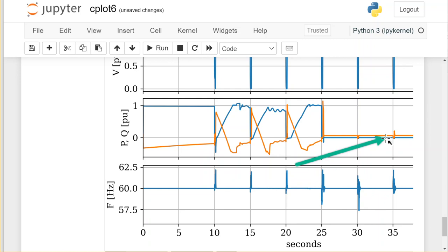So this is an informational test. It was stable down to a pretty low short circuit ratio. So in fact, right in this range here, the short circuit ratio was 3. And when it went down to 2.5, the plant did not come back. So this is a more severe scenario where we're having these faults occurring in between each transition.